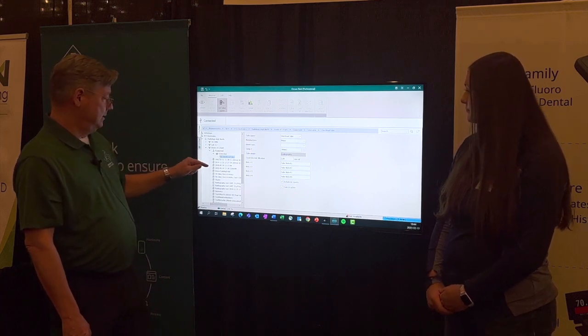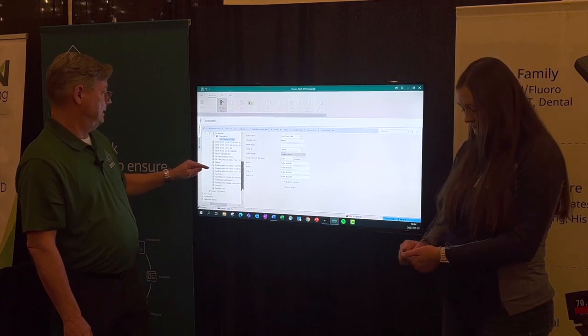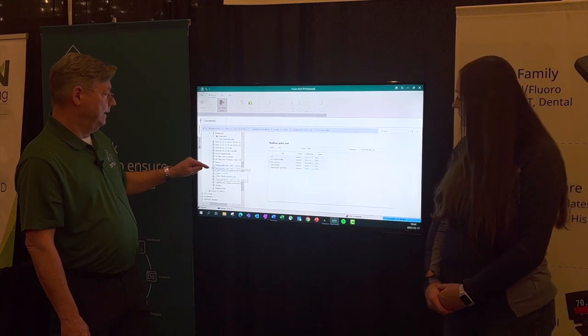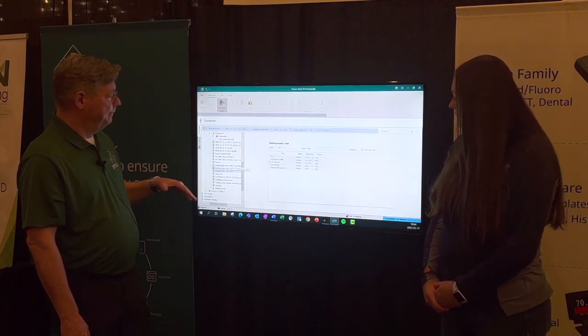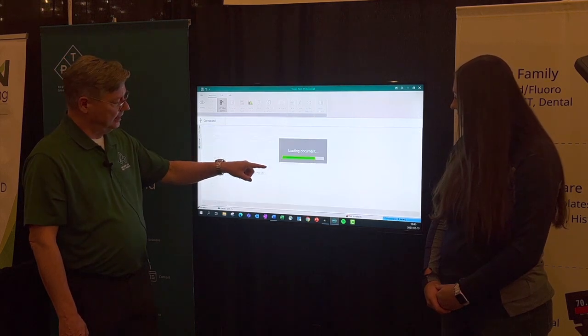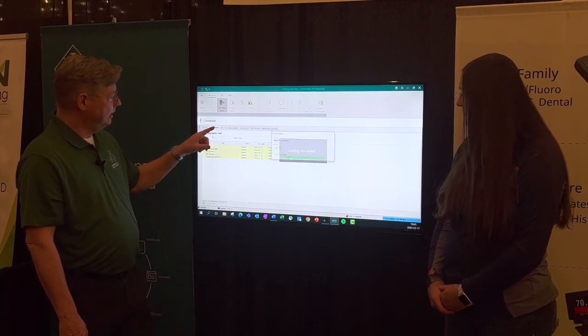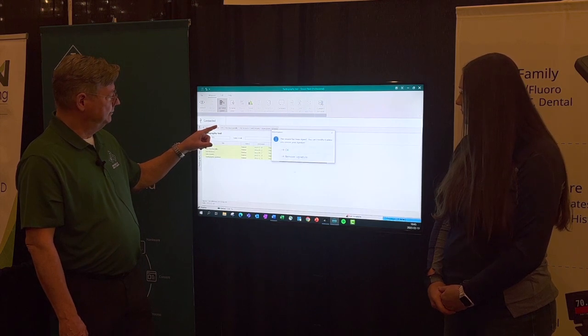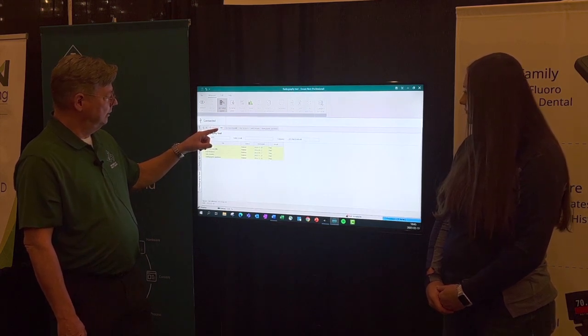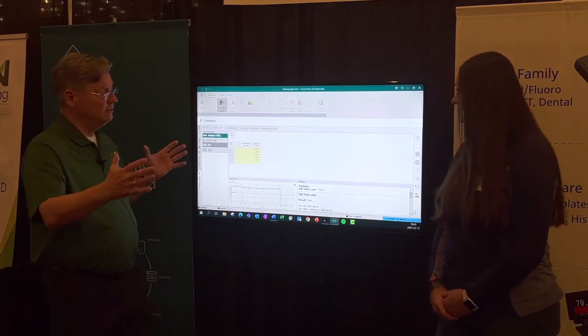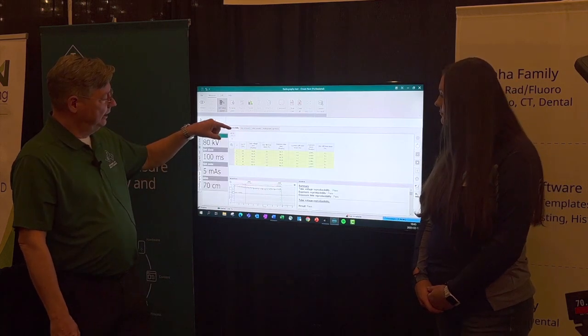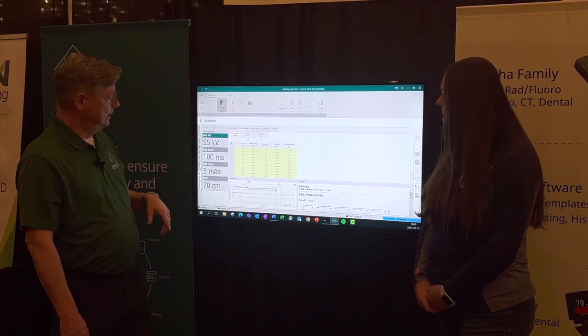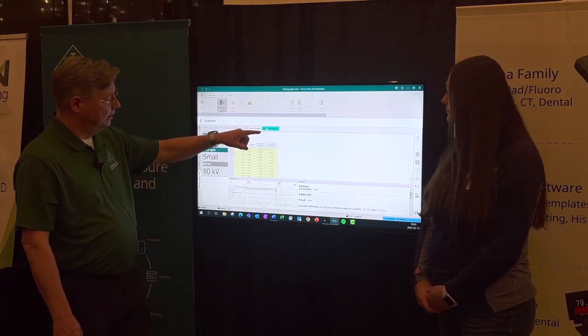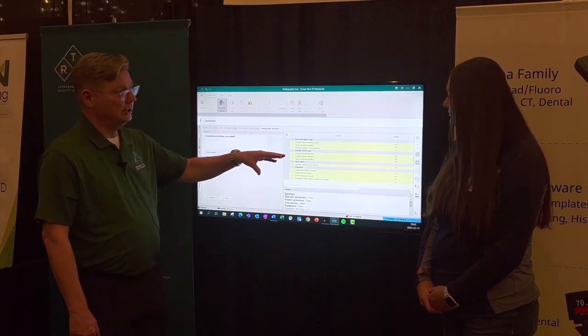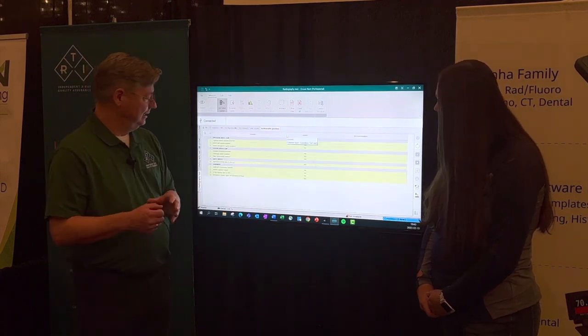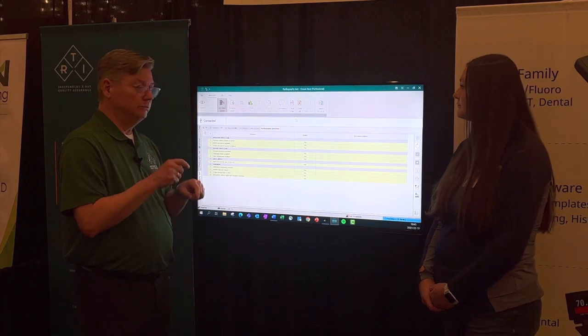So when we make a test, say that we look at a radiography test down there, maybe double click it, and then we'll have a test that is a multi-test template, where in one go we have HVL, and we can combine, like we said, you have a library of it, but you can combine those, so you have several in one go. HVL test, a KVP reproducibility, a KVP accuracy test, an mAs linearity test, and all those built in, and also the possibility to have and analyze questions, like a questionnaire, yes/no questions, so that we can not only connect the probes and collect data that way, but also during inspection.